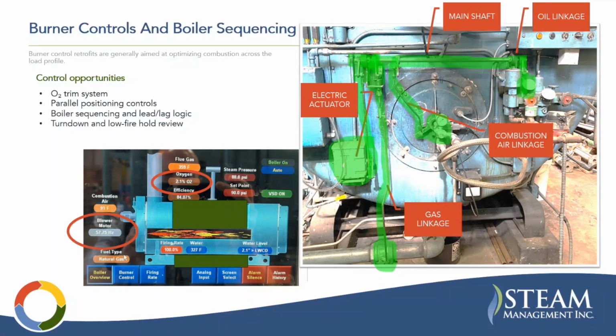Another scope is burner controls and boiler sequencing. As far as burner controls, upgrading a system like this, where it's called single point actuation, also sometimes called jack shaft controls, is basically a single electric actuator modulating this shaft, which is connected to the gas valve, the air dampers, and in this case, the fuel oil valve, all by linkages.